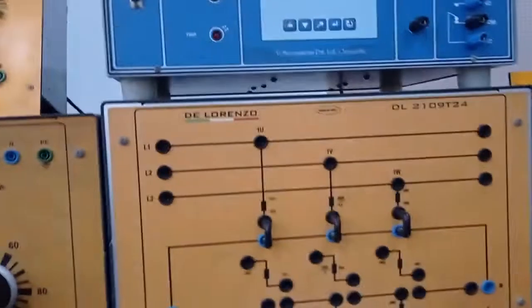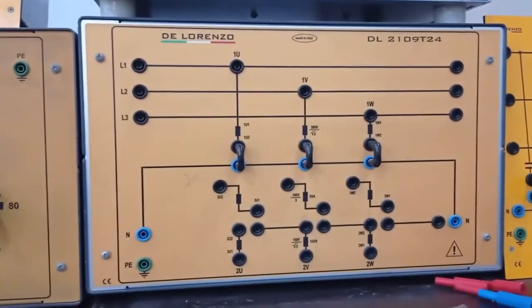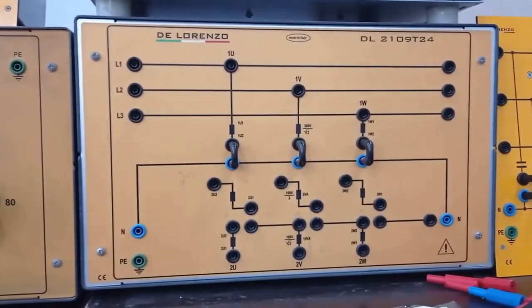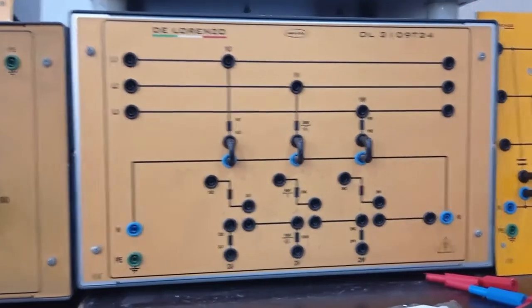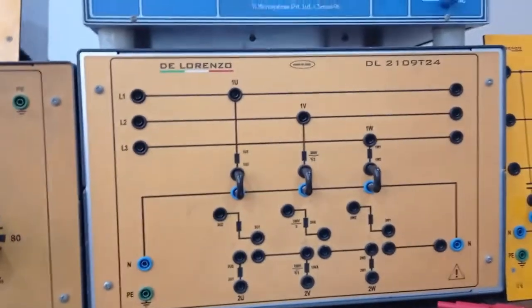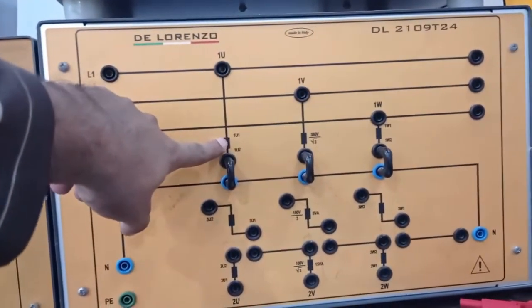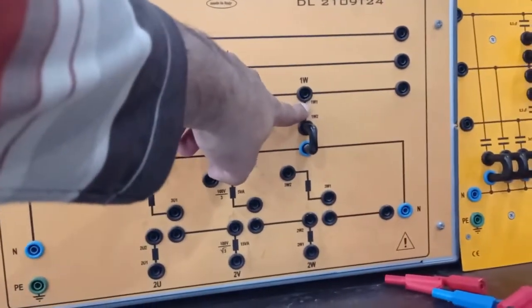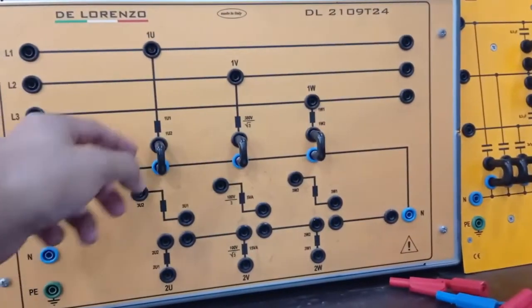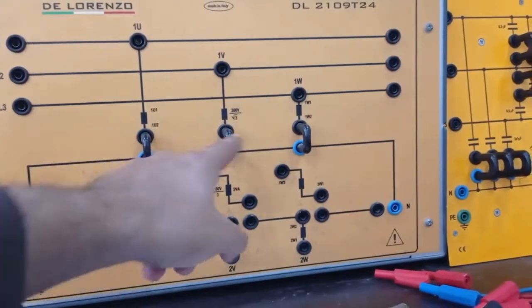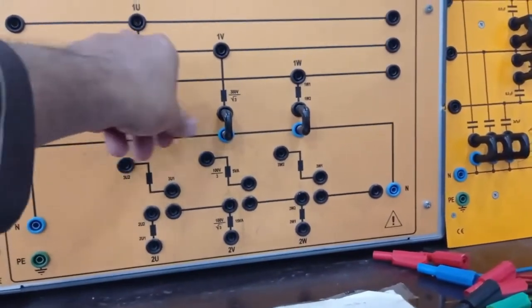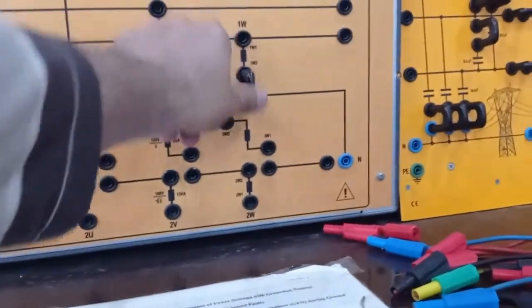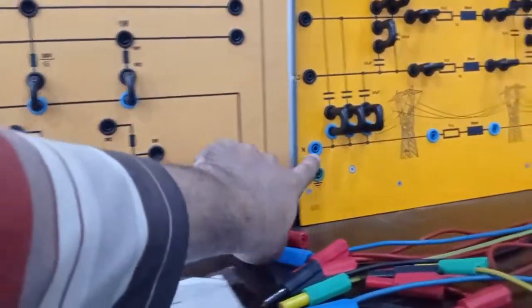Here is a three-phase voltage transformer. This three-phase voltage transformer has one primary and two secondary windings. The primary winding is over here. These three windings are already connected in Y configuration. This is the neutral point of that winding. Connect this neutral onward here.